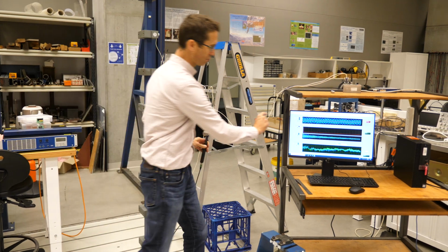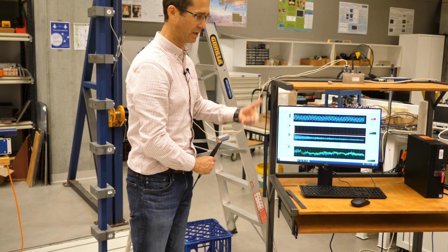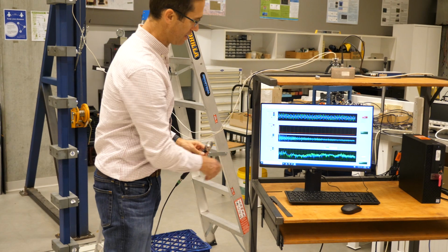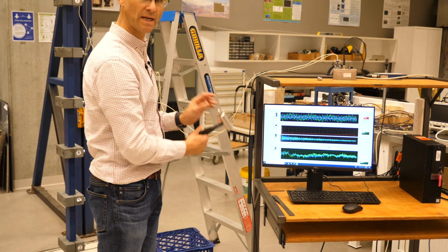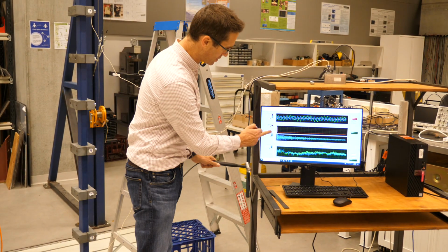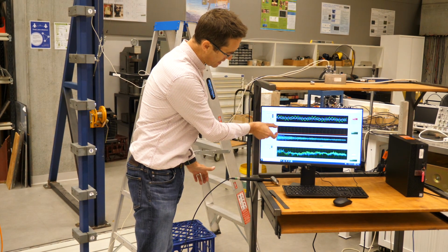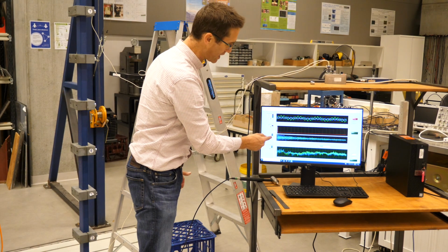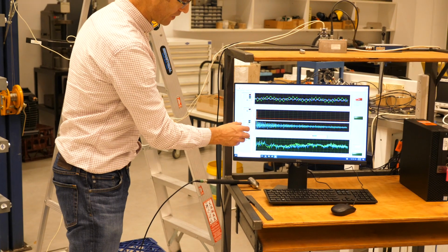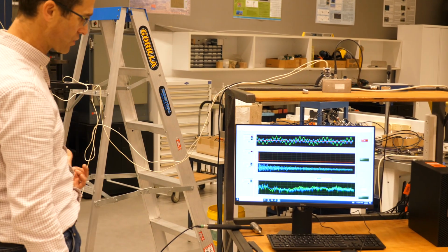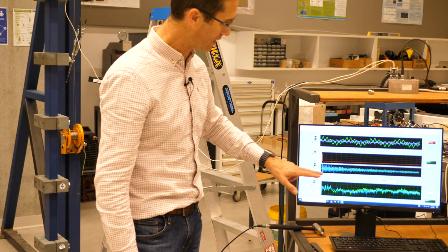So there you could see briefly we had 2 response measurements here, and this is scoping, so it's still buffering all the time, collecting new data. But those 2 measurements and that beep that we heard was to indicate that the measurement had been triggered based on the force measured by the force transducer, and although it'll be a little bit small in here, there's an impulsive event here on the force transducer channel, which is this red curve. The 2 curves below in green and blue here are the responses of each of the 2 reference transducers, one at level 7, one at level 1, and they're obviously different to one another.